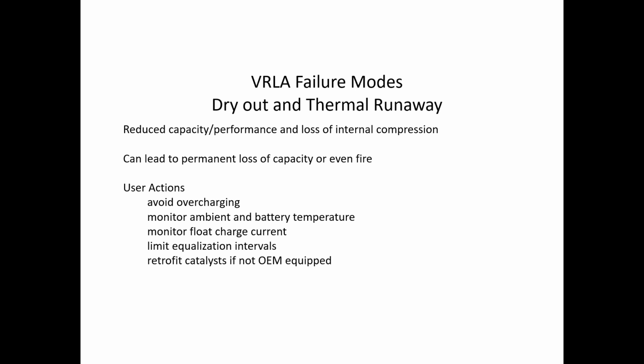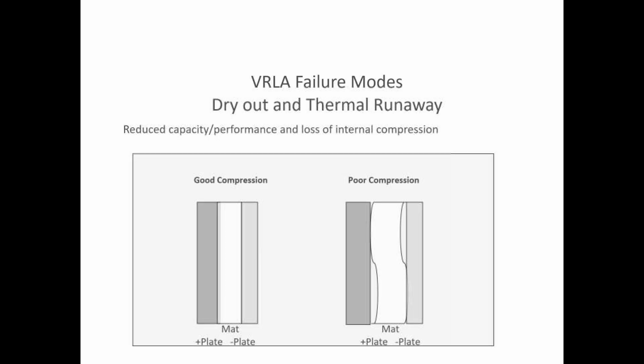And there is a catalyst option available for valve regulated batteries. I mentioned before the hydrogen and oxygen coming off the positive plate being recombined on the negative. I'll touch on this again a little later in this slideshow, but there's a catalyst that some manufacturers supply and others can be retrofitted with. The material is palladium, and it's affixed to the pressure release valve. Instead of the hydrogen and oxygen recombining on the negative and then underpolarizing or undercharging the negative, they recombine in the headspace of the cell and re-wet from the top of the cell, and that wicks through the battery and helps extend the life of these batteries. Again, I'll touch on that a little later, but that's another option.